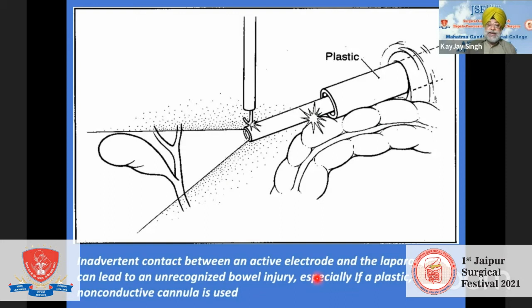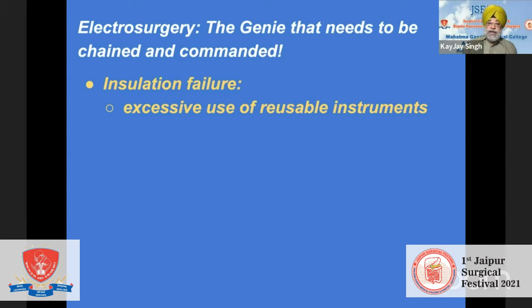The third way the electrosurgical unit can fail and deliver a disaster to our patient is insulation failure. Insulation failure happens because of excessive use of reusable instruments, repetitive passage through trocars, and frequent mechanical and chemical enzymatic sterilizations. They inherently damage the insulating sheaths of instruments. It is very important to actually inspect.